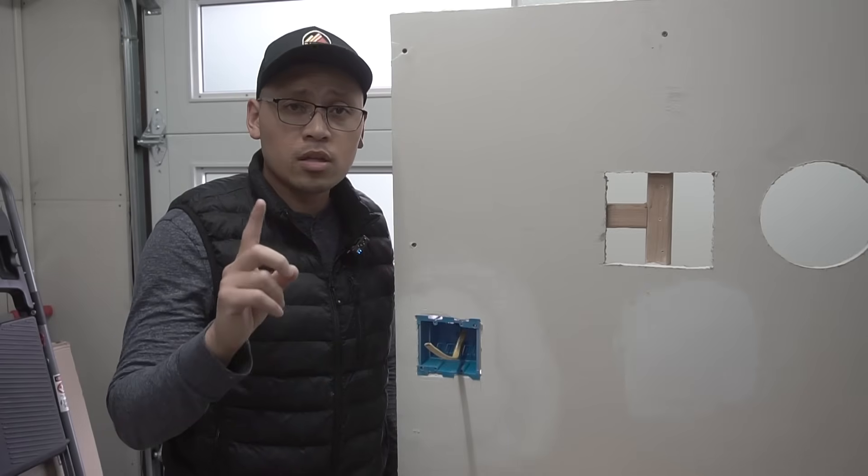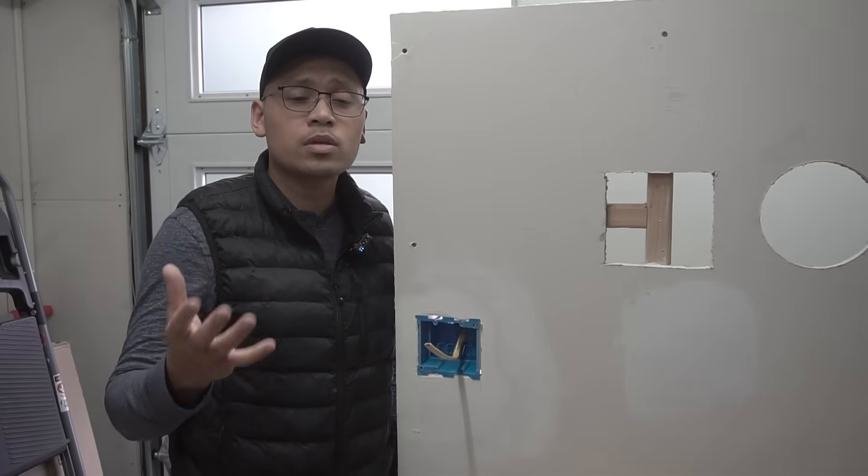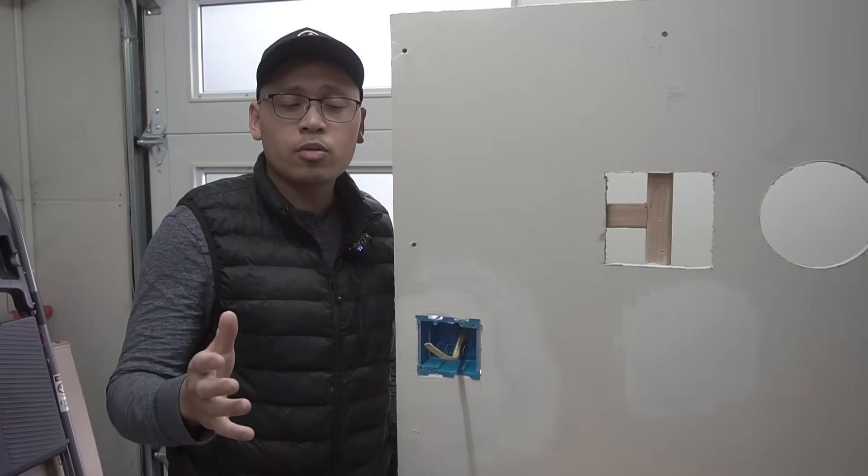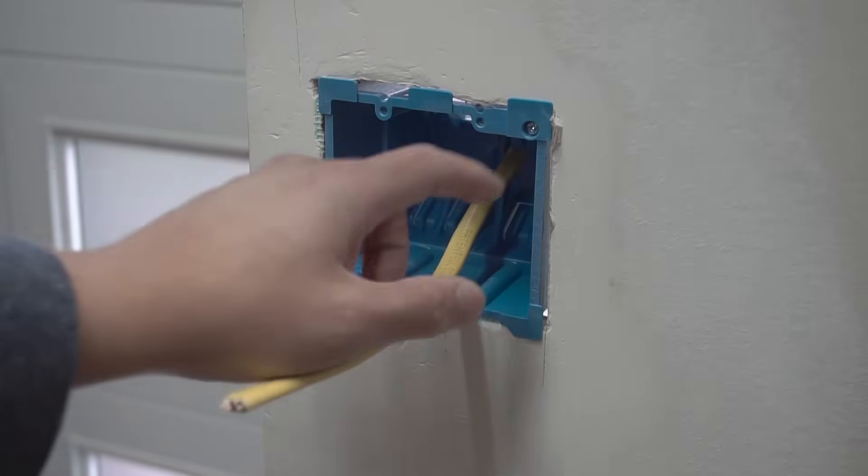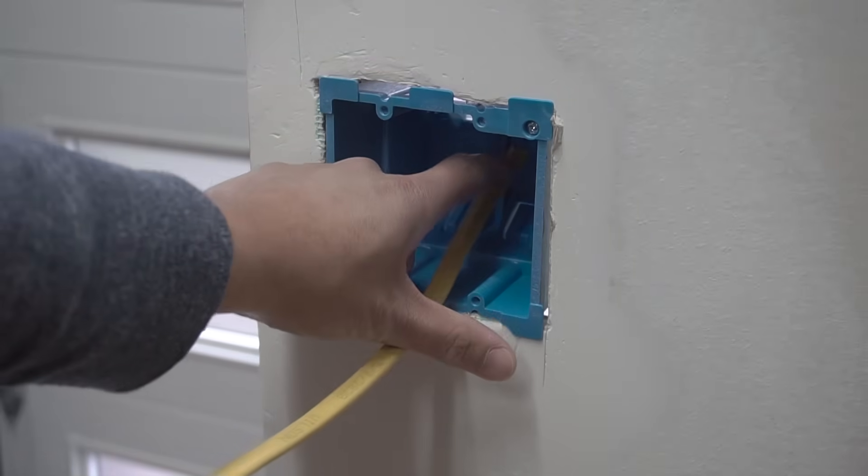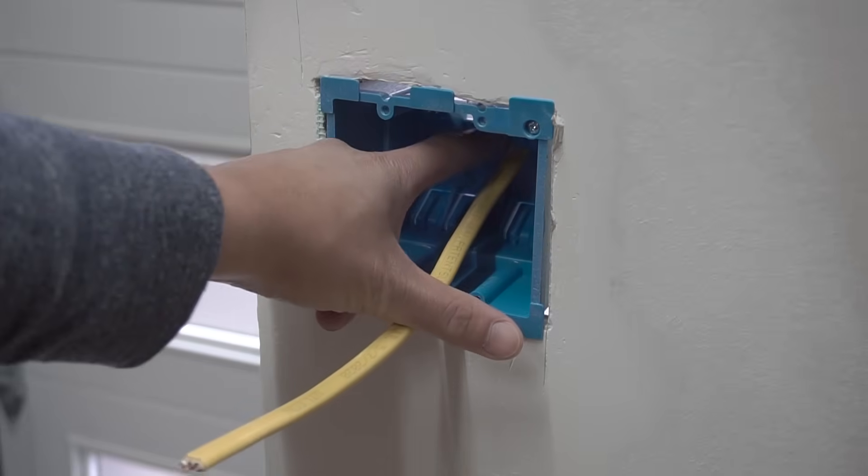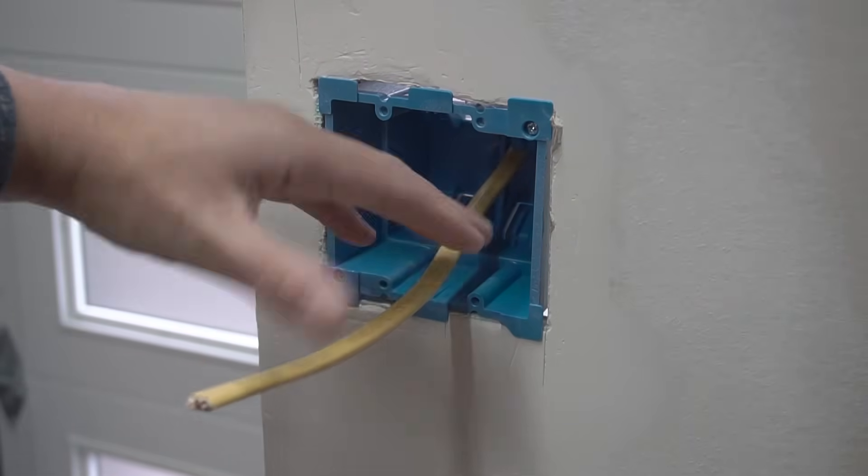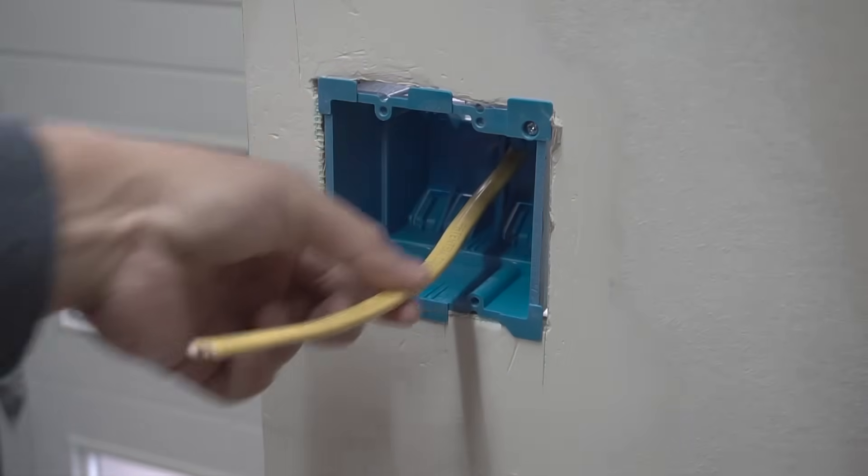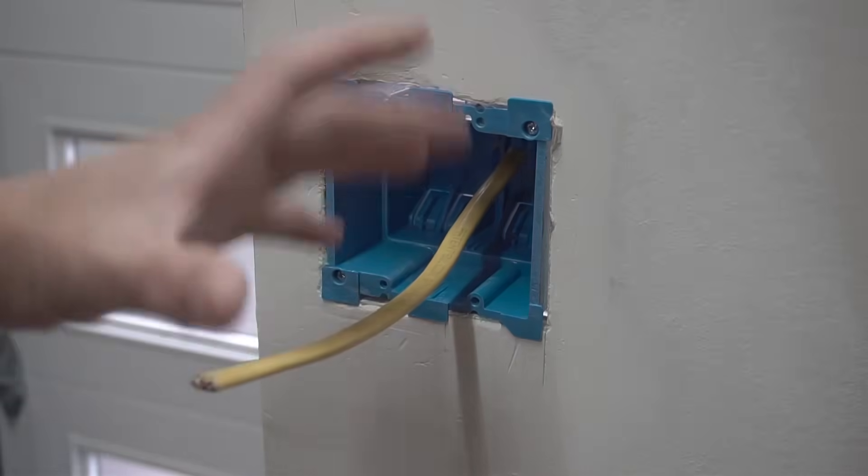So with that being said, let me show you method number one, which is probably the easiest and the most common way that we do it. So if you're not yet familiar with the code, you have to leave at least a quarter inch of sheathing past the clamp of where it enters through the box. Leave at least six inches of wire past the box, and leave three inches of length of cable.